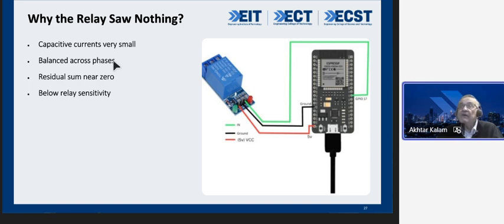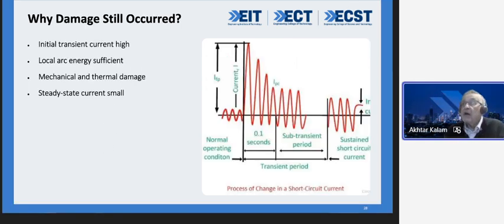Then why did the damage still occur? Because look at that, there's the initial transient current. Initially, it goes very high, 3 to 4 times the steady state value. Local arc energy is sufficient. Mechanical and thermal damage can be done, and the steady state current is still very, very small. That's a steady state value. So the transient effect can cause real damage. By the way, the transient effect is for a very short period of time, at a very high value, and this can cause damage even when the steady state system value looks harmless.